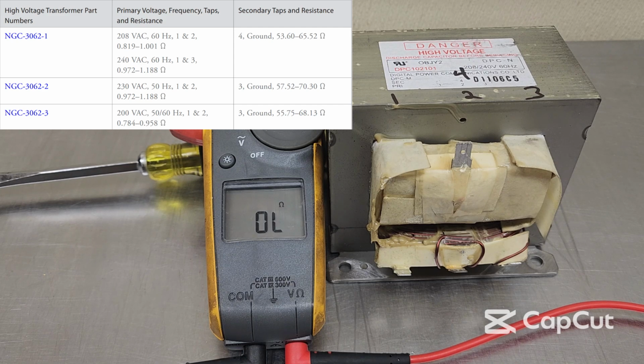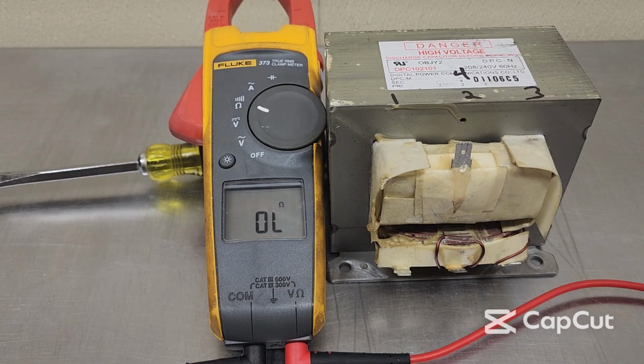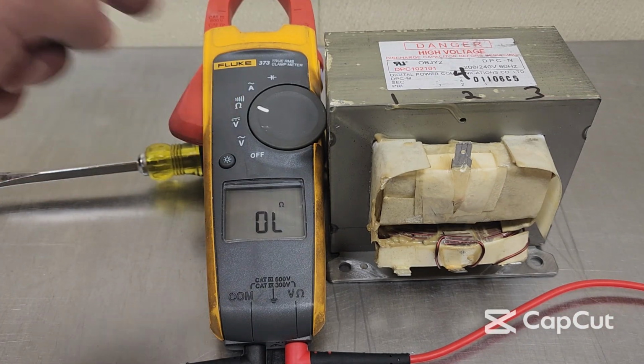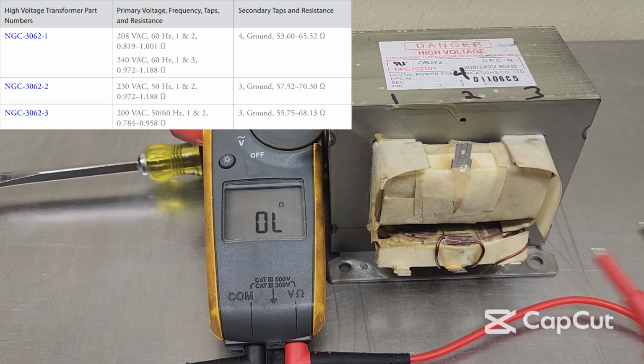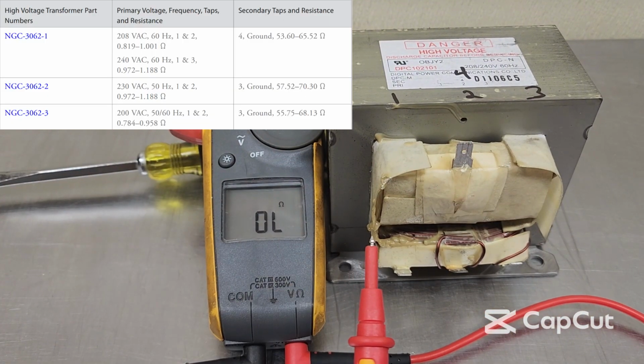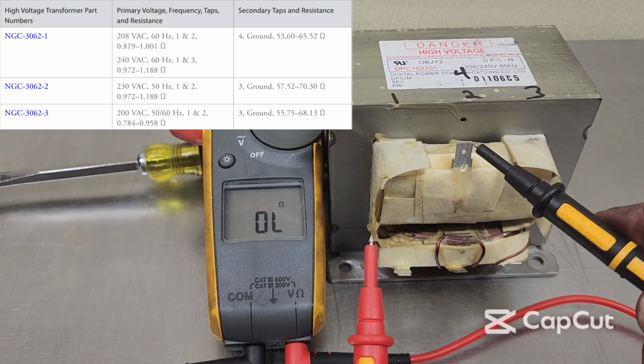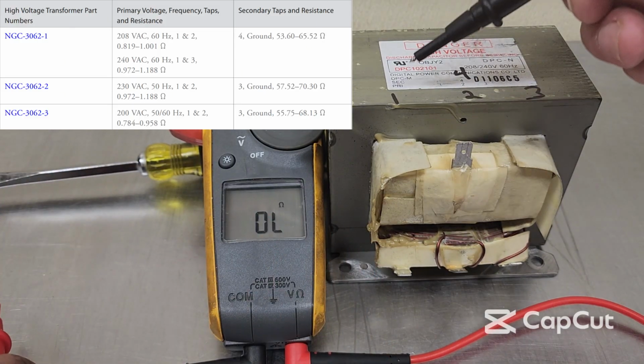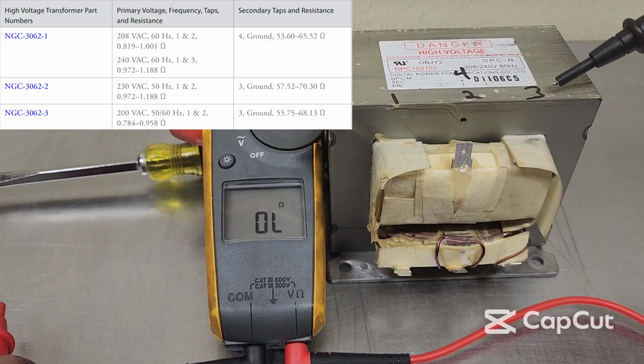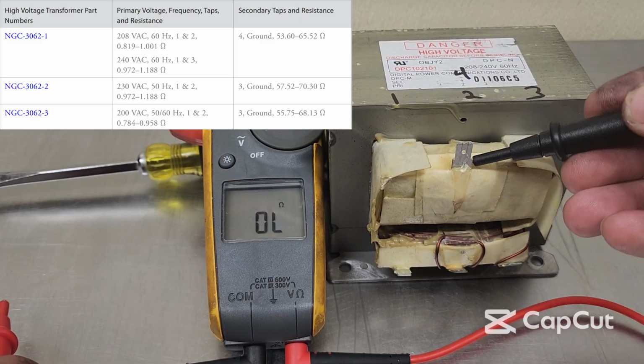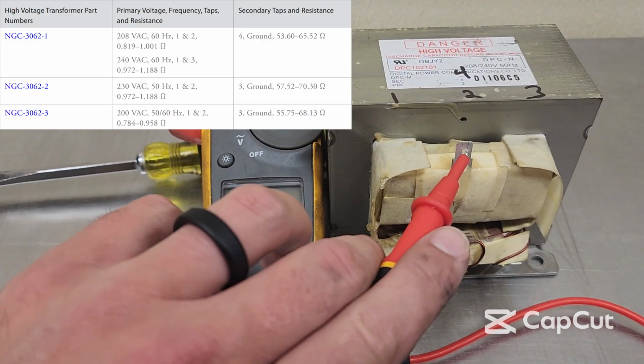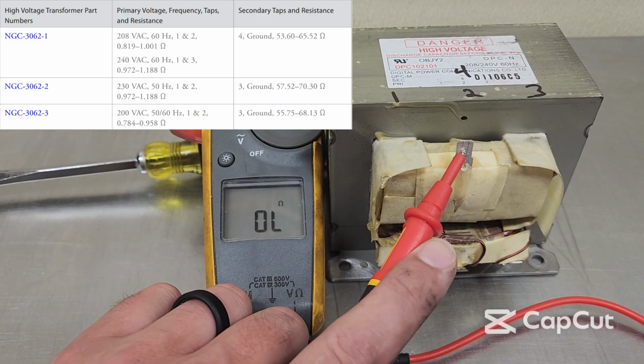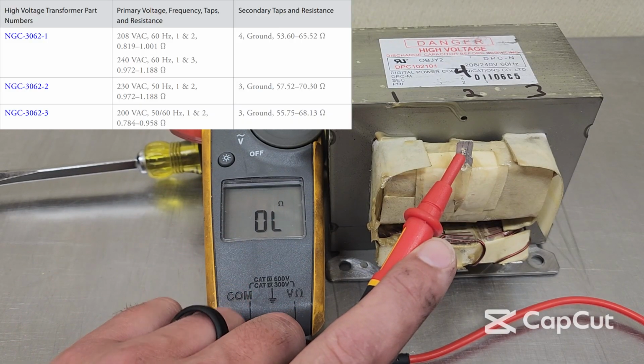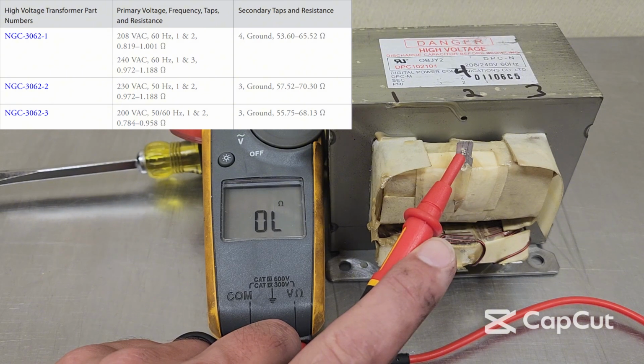So with this transformer, we are going to test a couple things. Currently we are in ohms, which is our horseshoe, and we are checking for a couple things here. First of all, number 4, so I've labeled it up top. We have tap 1, tap 2, tap 3, and tap 4. Tap 4 is the one that you never want to test if you have voltage on the oven. This is going to be your output essentially, or your load side.